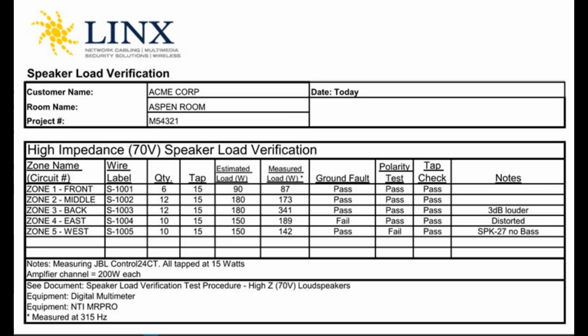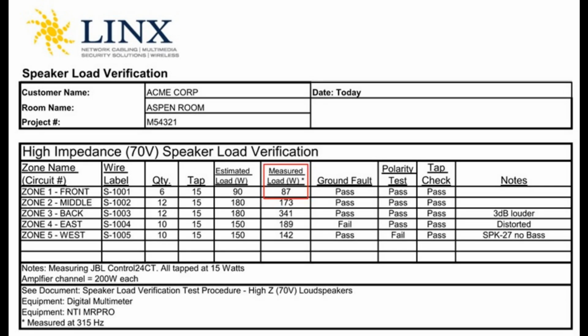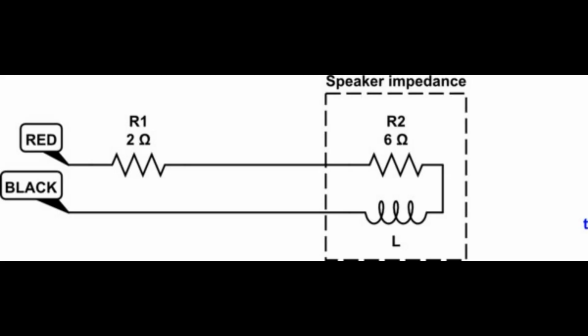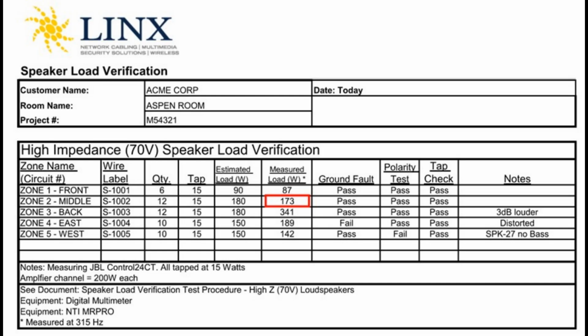Here is an example speaker load verification form filled out. Let's find out what we can tell from these results. The Zone 1 measured value is 87 watts. This looks normal. Remember, the measured values can be up to 20% off, in some cases. The reason for this is that impedance value will depend on the frequency, wire gauge, and wire length of the speaker circuit. The Zone 2 measured value looks normal.